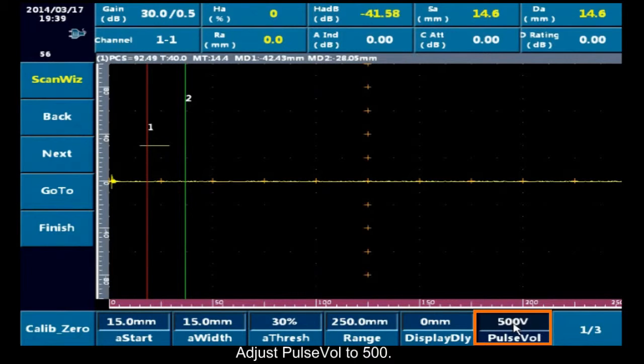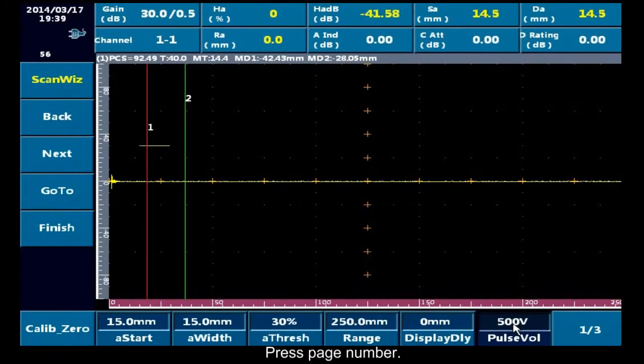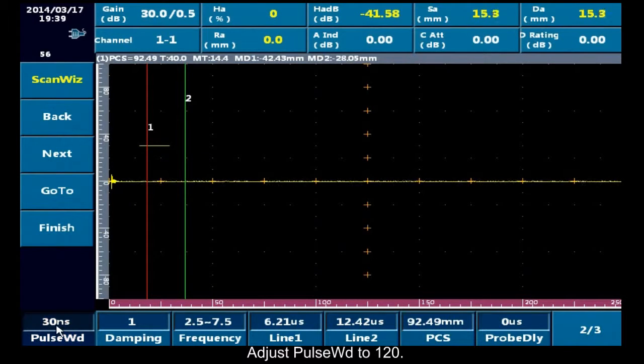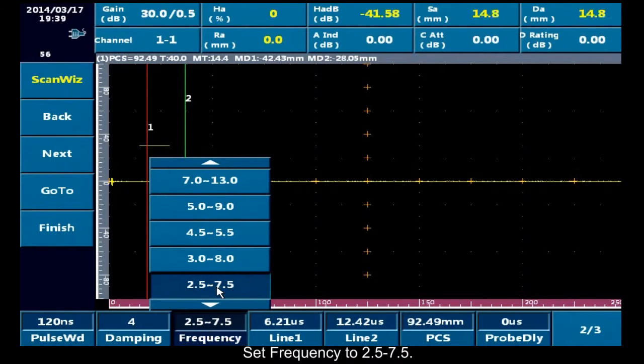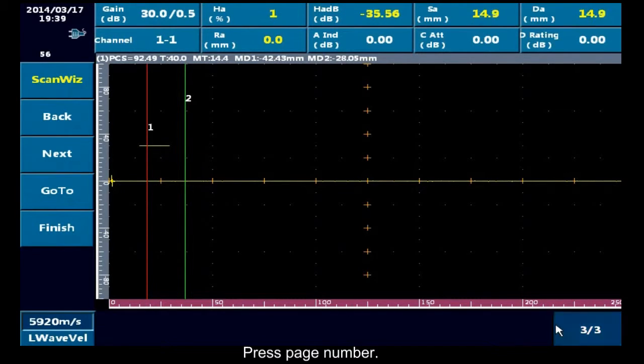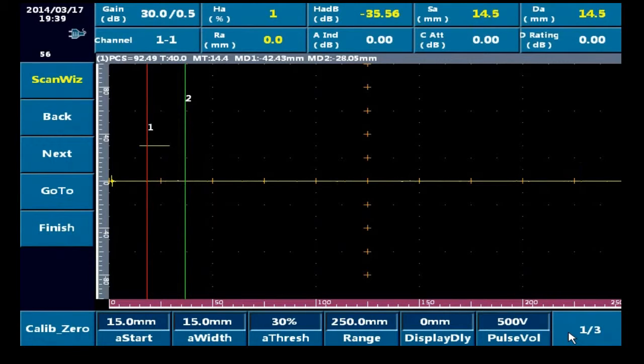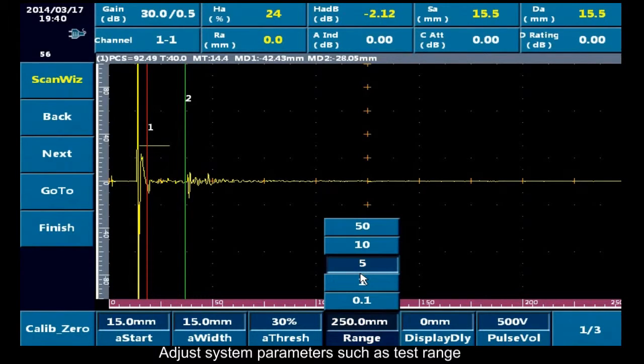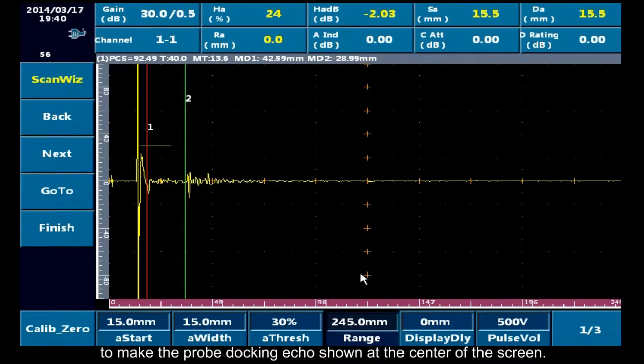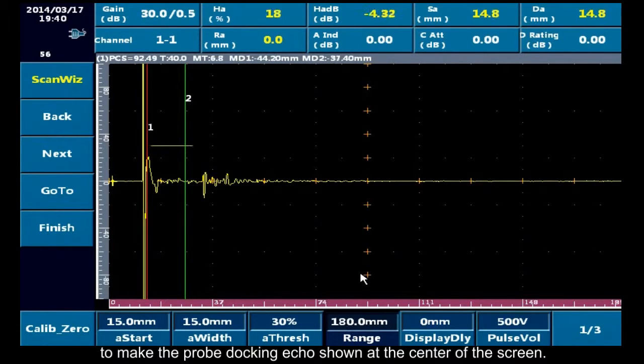Adjust pulse voltage to 500. Press page number. Adjust pulse width to 120. Adjust damping to 4. Set frequency to 2.5 to 7.5. Press page number. Dock to TOFD probes. Adjust system parameters such as test range to make the probe docking echo shown at the center of the screen.